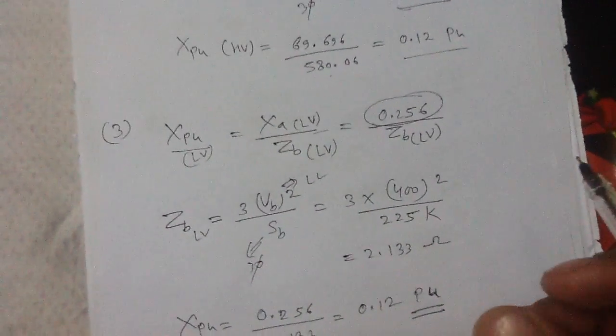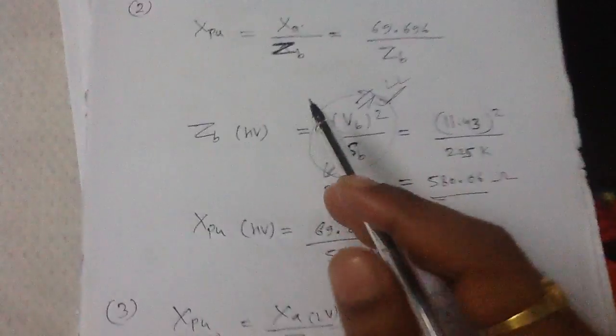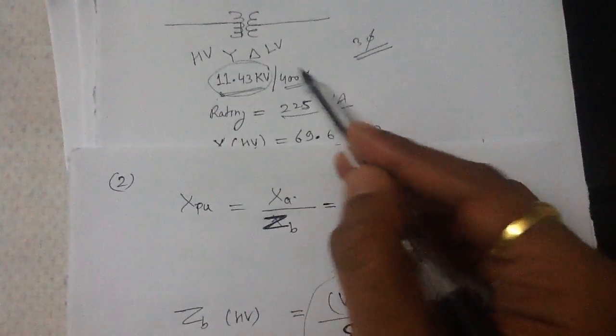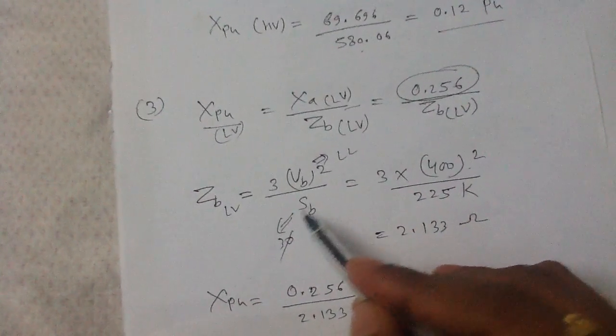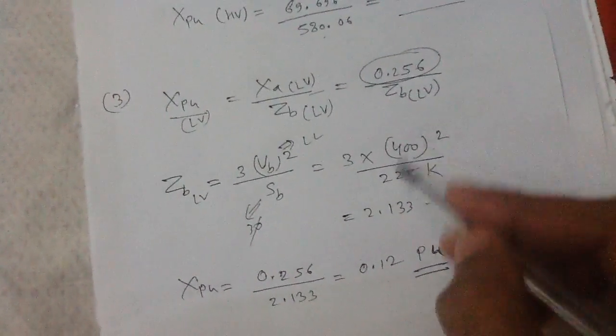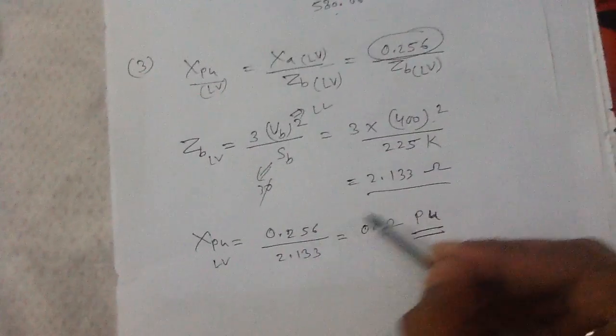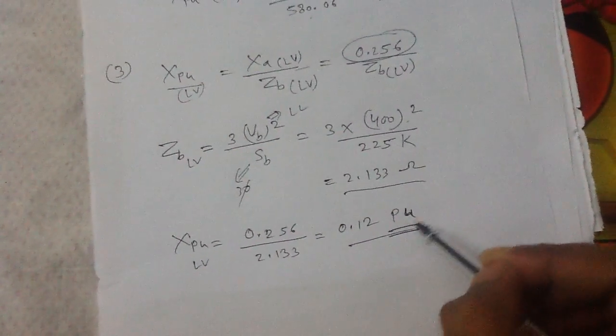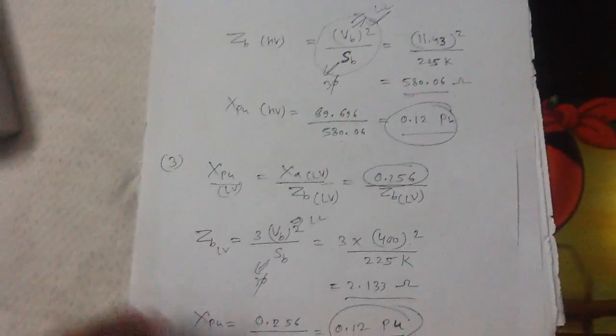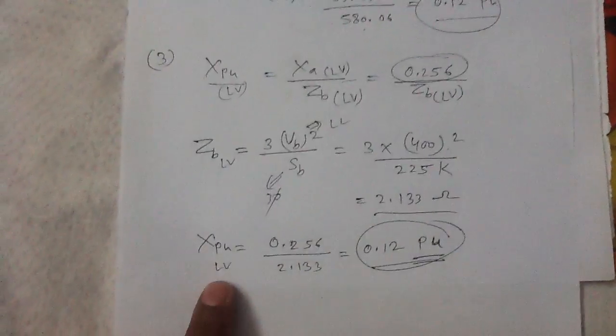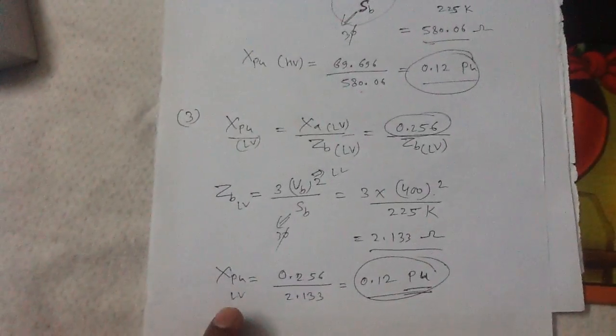The base impedance on the LV side equals 400 volts squared divided by the power rating of 225 kVA, which gives 2.133 ohm. The per unit reactance referred to the LV side equals 0.256 divided by 2.133, giving 0.12 per unit. This is very important: the per unit reactance referred to the HV side and the per unit reactance referred to the LV side are the same for a transformer.